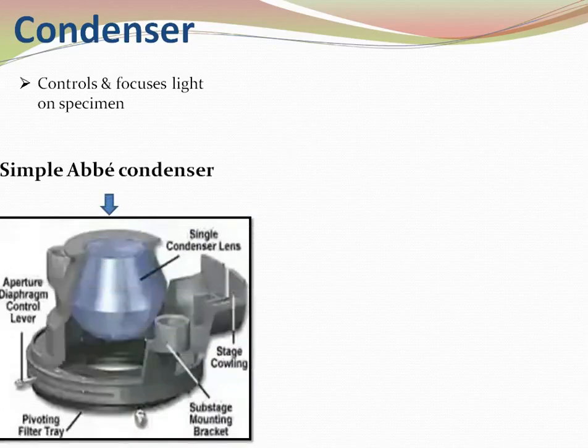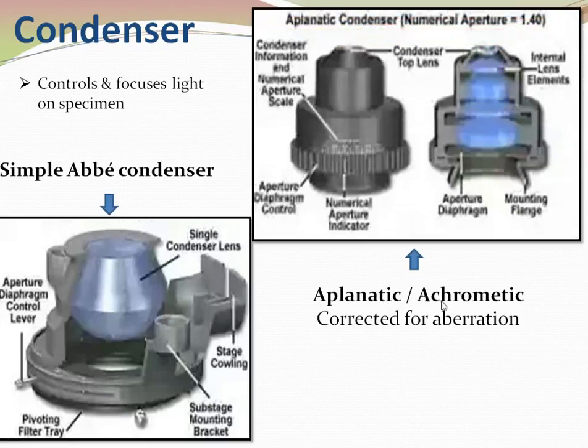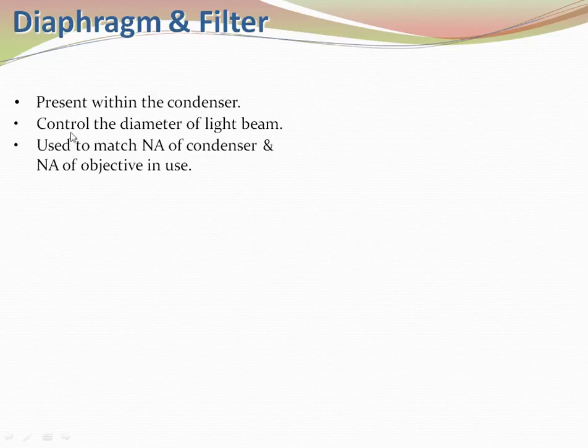The condenser's function is to control and focus the light on the specimen. There are two types: the simple condenser, which has a single lens with diaphragm control, and the achromatic or aplanatic condenser, which is a combination of lenses with a diaphragm and mounting thread. The diaphragm is present within the condenser and controls the diameter of the light beam. It is used to match the NA of the condenser and the NA of the objective.